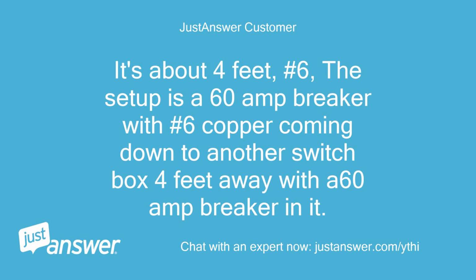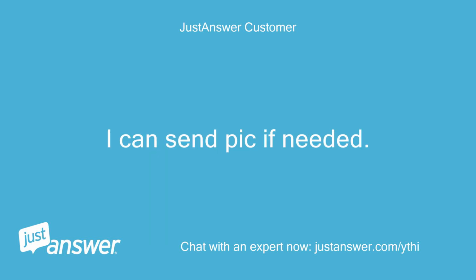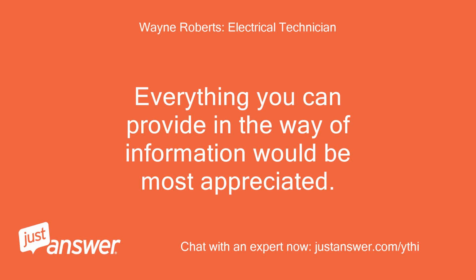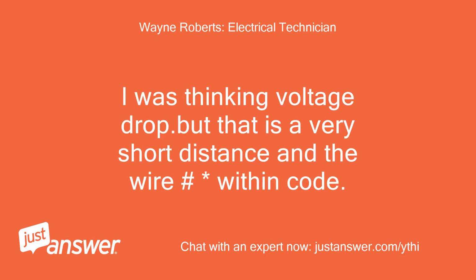The setup is a 60 amp breaker with number 6 copper coming down to another switch box 4 feet away with a 60 amp breaker in it. I can send pic if needed. Everything you can provide in the way of information would be most appreciated. I was thinking voltage drop. But that is a very short distance and the wire is within code.